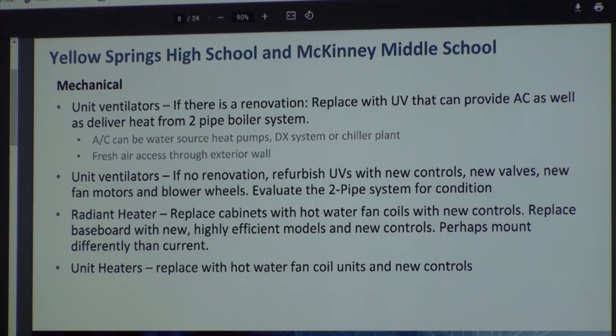If you don't want to use those for air conditioning, the ones you have can be refurbished. You can put new motors in them, high efficiency DC motors, and replace the fans. At a minimum, you need to go through and replace the controls and the control valve and clean the coils. The coils I saw look great - they could continue to be used. Like I said, they last; they're really pretty simple machines, just a hot water coil and a fan.